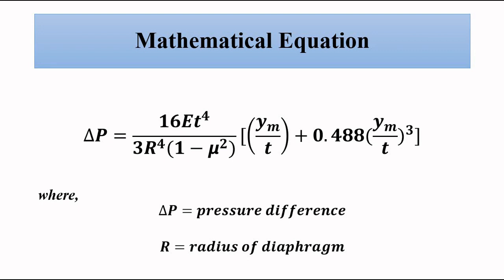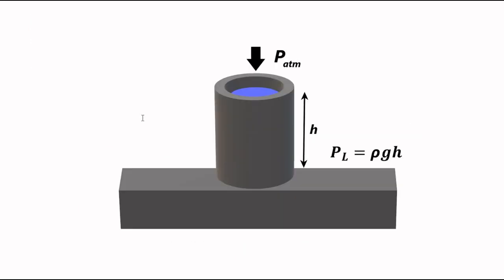Now we have to use it for measurement of the level of a liquid column. So like bellows and the Bourdon tube, the principle is the same. When we have a certain liquid in a container, in a tube or whatever, because of its height above the reference or datum position, it will exert some pressure. That pressure is P_L equal to rho g h. Rho is the density of the liquid, g is acceleration due to gravity, and h is the height of the liquid from the reference position. This is the reference level, the horizontal position from that edge.